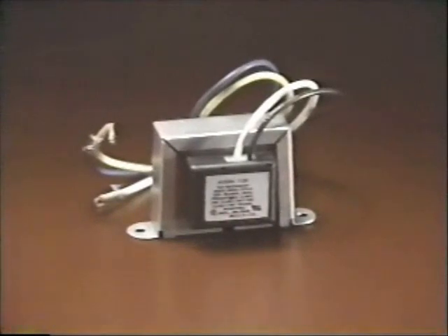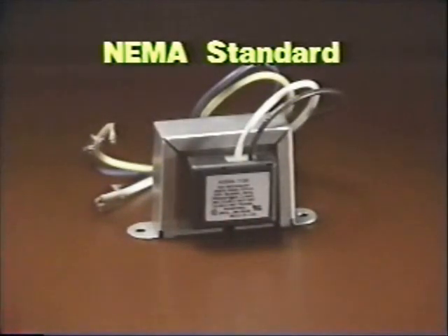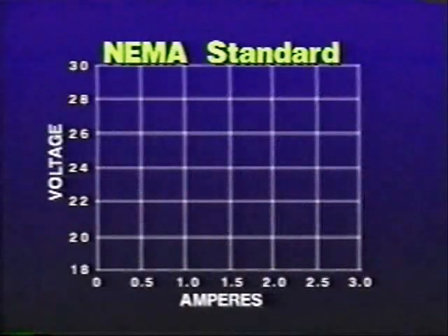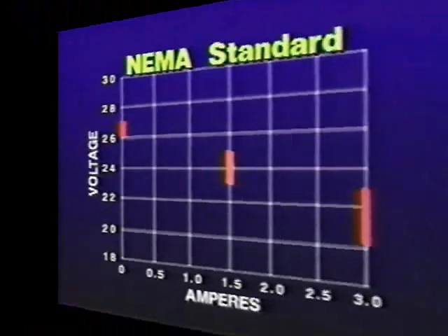The simplest way to avoid problems with voltage regulation is to select transformers that meet the NEMA standard for Class II transformers. The key requirement of the NEMA standard limits the amount of output voltage drop-off allowed as the load on a transformer increases. At 100% of rated load, a transformer must hold its voltage within 1 volt of its 24-volt rating. Open circuit voltage must be within a half volt of its 26.5 rating. At 200%, it must be within 1.5 volts of its 21.5 volt rating.